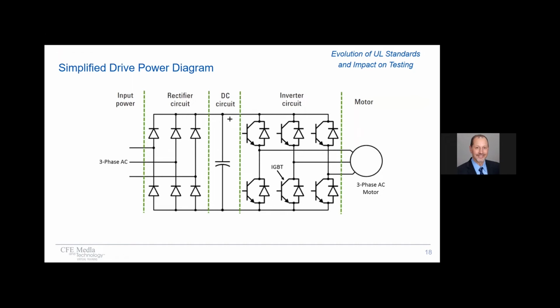Before going further, let's briefly review a typical power design for a variable speed drive. On the left, we have the rectifier section, which converts AC to DC. In the middle, we have what's called the DC bus or DC link, which filters and actually stores energy. And on the right, we have the inverter section, which converts the DC back into variable AC so that the motor can be controlled.